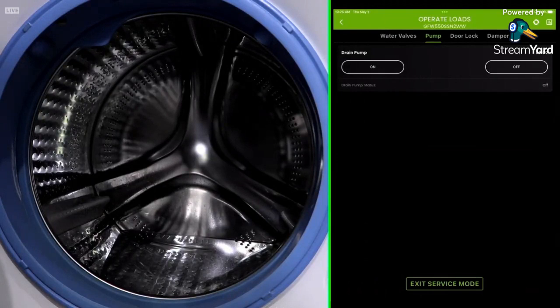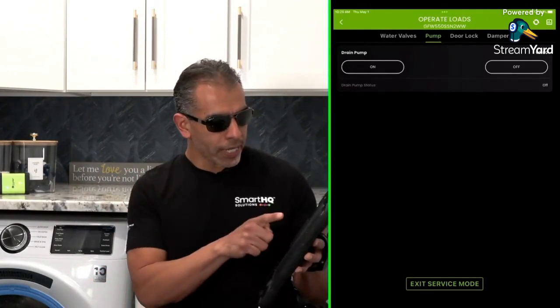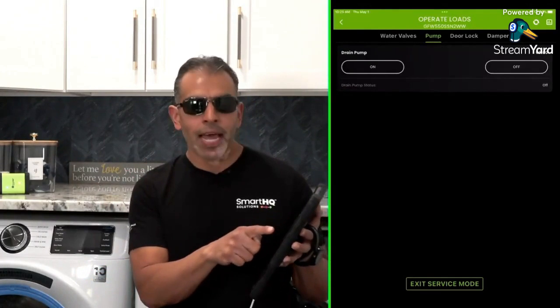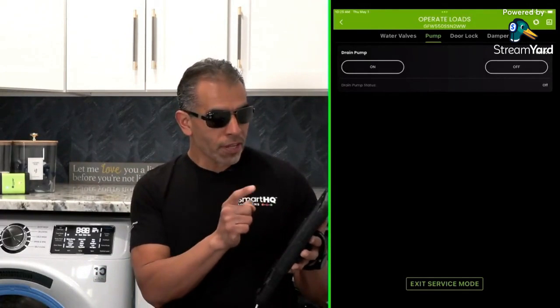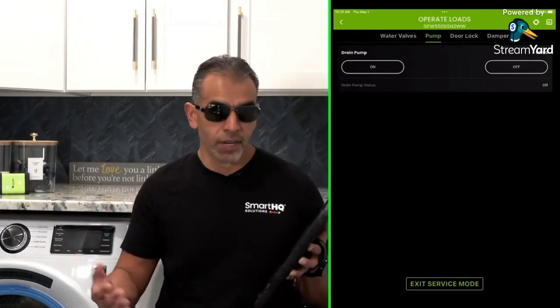Two very important things I want the audience to observe. When we activate a component, take a look at the status. The drain pump status right now is off. When I turn this component on, I should see that status change from off to on. This indicates that my main control board is sending voltage, in this case 120 volts AC, to the drain pump in order to activate it. And of course, I should see the water begin to come out.